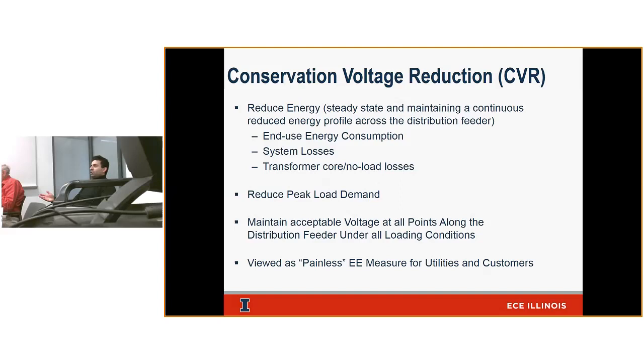When you maintain acceptable voltage at all points along the feeder, you are trying to stay out of violations. You could also correct any other voltage problems when you try to implement conservation voltage reduction. For example, our engineers doing voltage optimization will have to study the circuit, find out we're delivering high voltage at some points, and correct that. We have the tools to do something about it.